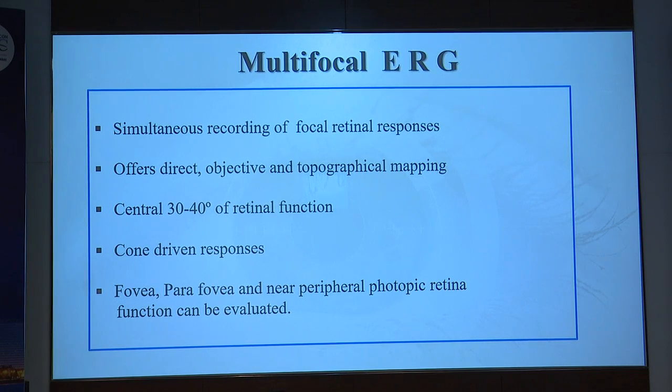In multifocal ERG, there is a simultaneous recording of the focal retinal responses. It offers direct, objective, and topographical mapping. It records the central 30 to 40 degrees of retinal function. It is a cone-driven response, and the fovea, parafovea, and near peripheral photopic retina function can be evaluated.